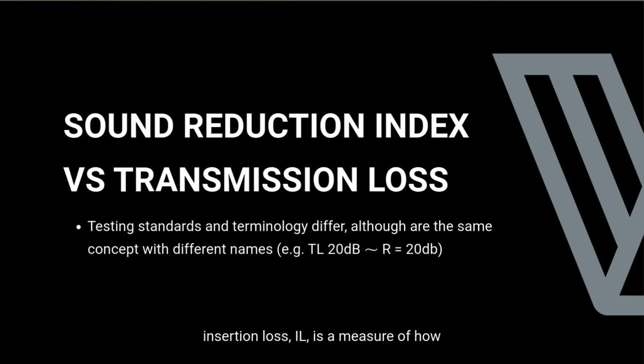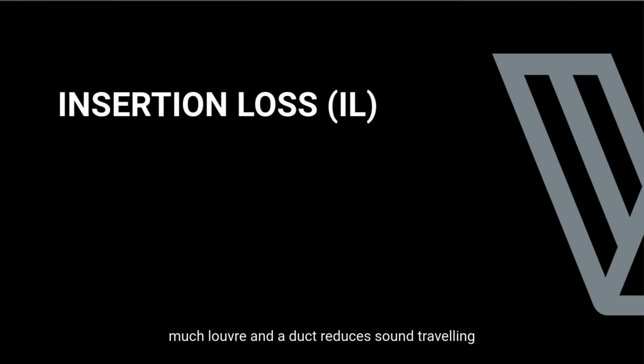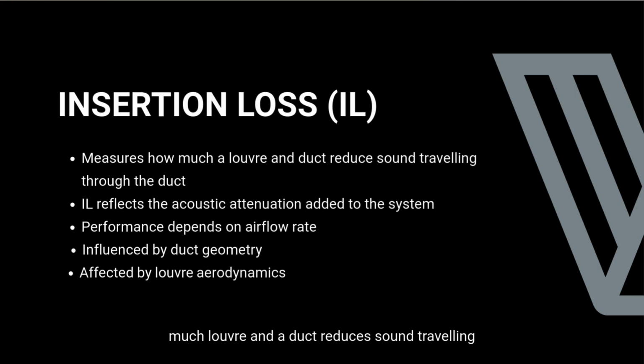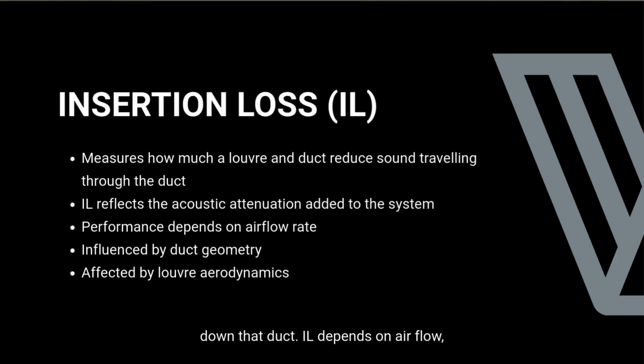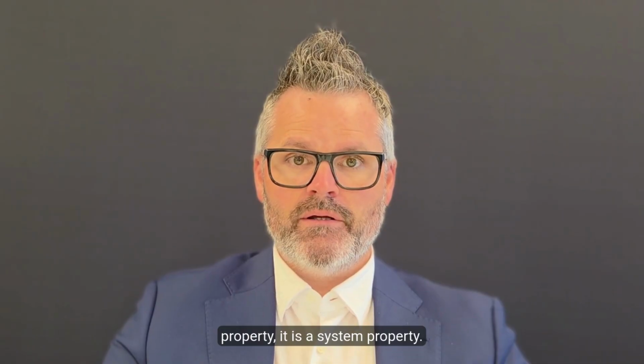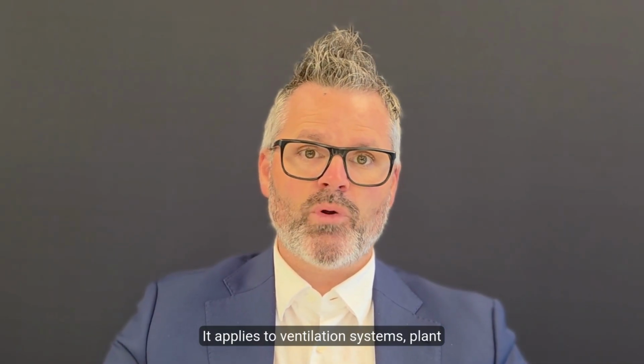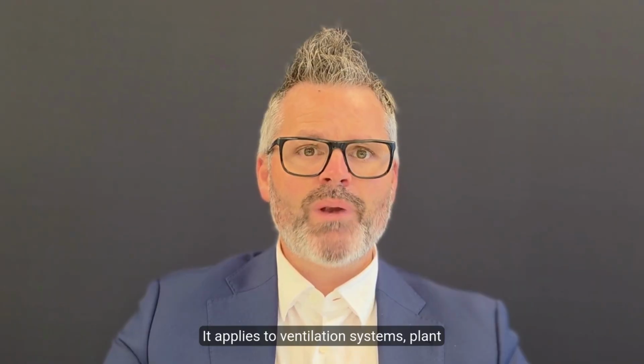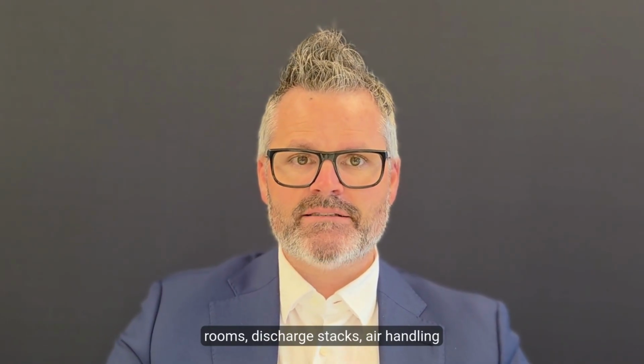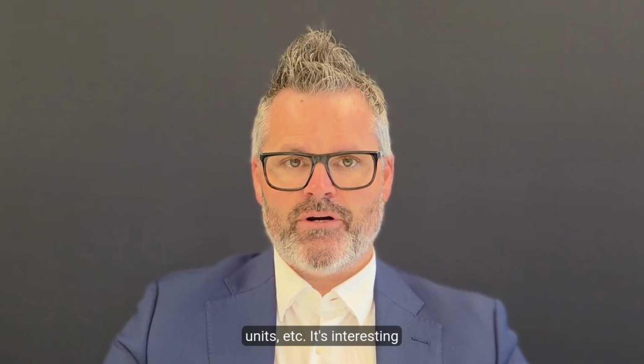Lastly, insertion loss, IL, is a measure of how much a louver in a duct reduces sound travelling down that duct. IL depends on airflow, duct geometry, and louver aerodynamics. So importantly, it is not a material property, it is a system property. It applies to ventilation systems, plant rooms, discharge stacks, air handling units, etc.